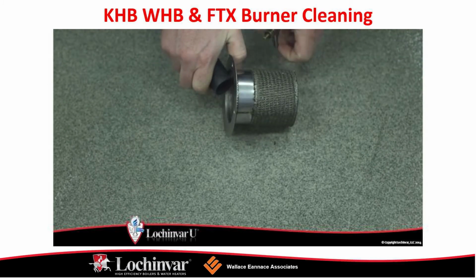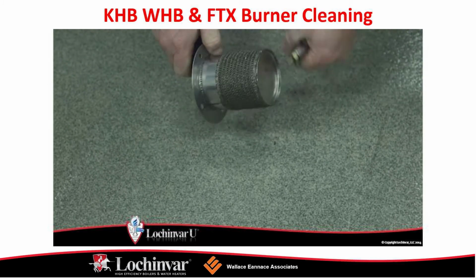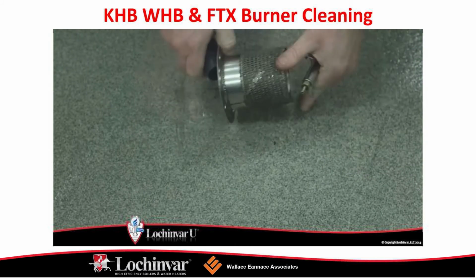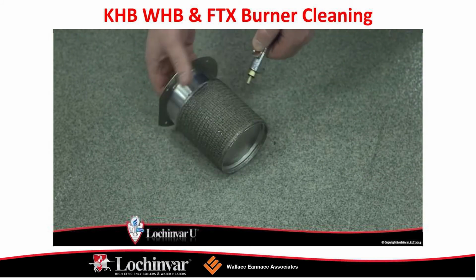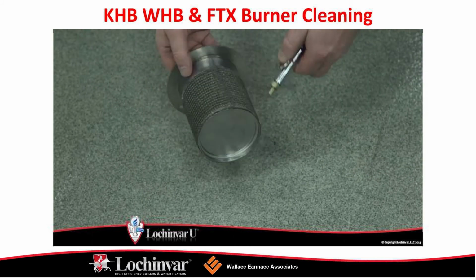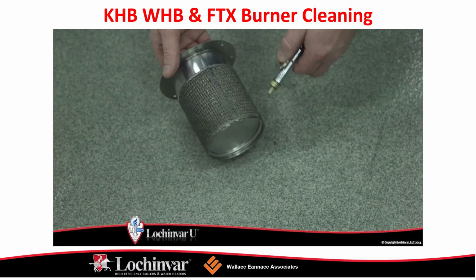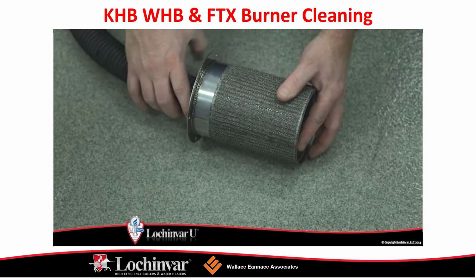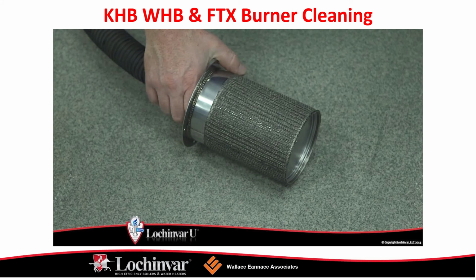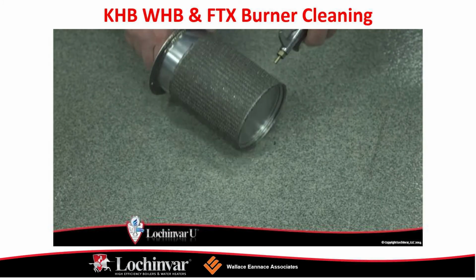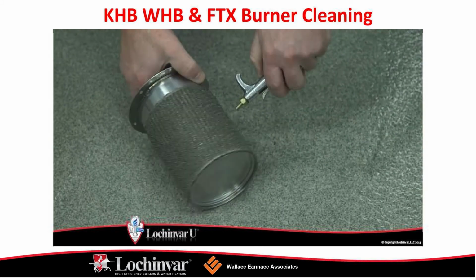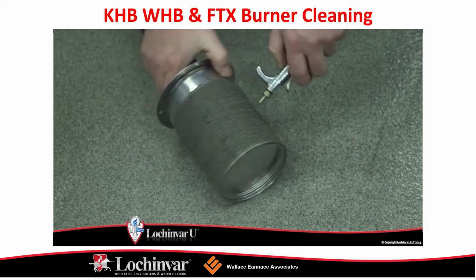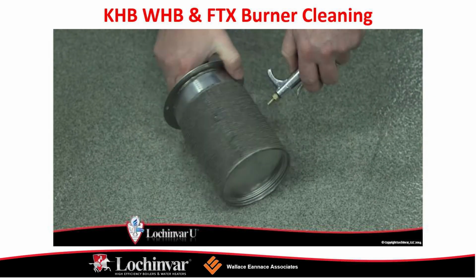Using a Torx wrench, remove the screws securing the igniter and flame rod to the heat exchanger door, and then remove. Now remove the insulating refractory from the heat exchanger door. Be sure to inspect the insulating refractory for damage. If the refractory is damaged, it must be replaced.